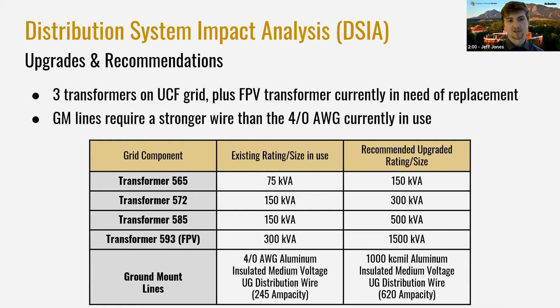The final row here is not an upgrade to existing electrical infrastructure, but a recommendation for the proposed trench lines that will need to be run out to the ground mount system. We found that to get rid of thermal overloads on these new ground mount lines, we had to define it as a 1000 kcmil wire instead of the typical 4/0 gauge used throughout the rest of the grid at UCF. With all these upgrades in place, we do not anticipate any major issues interconnecting our systems.